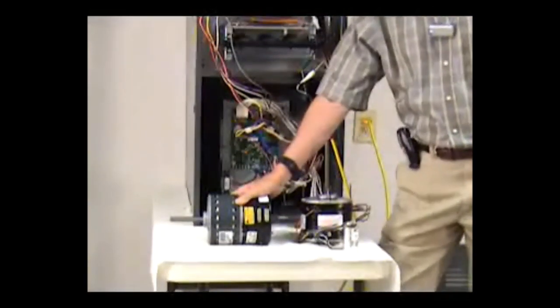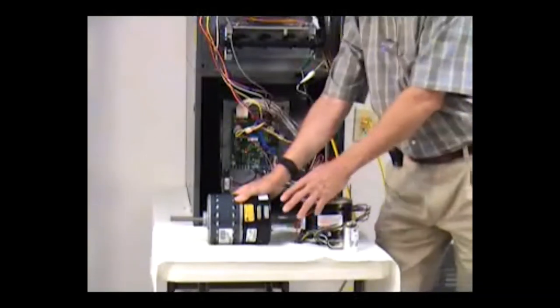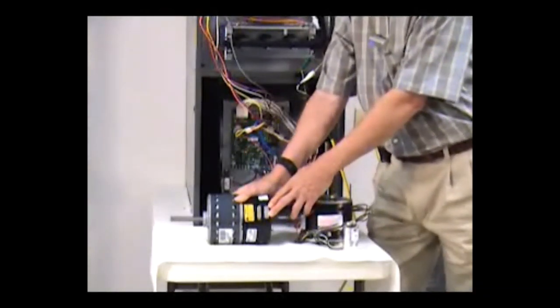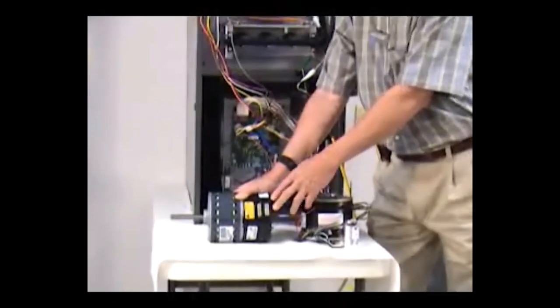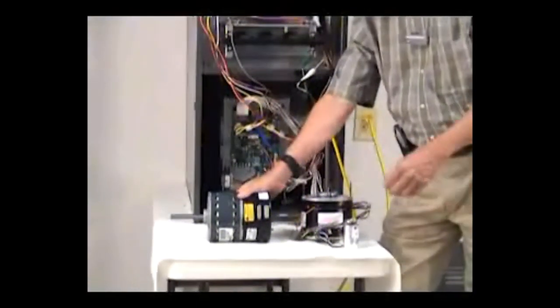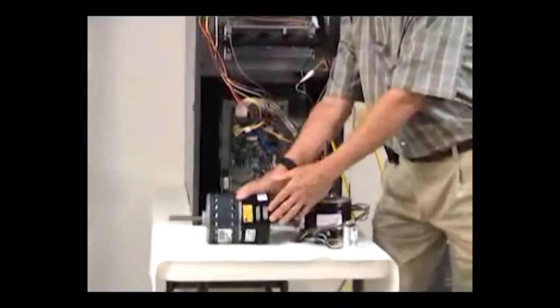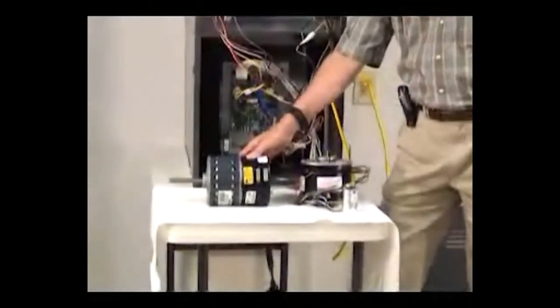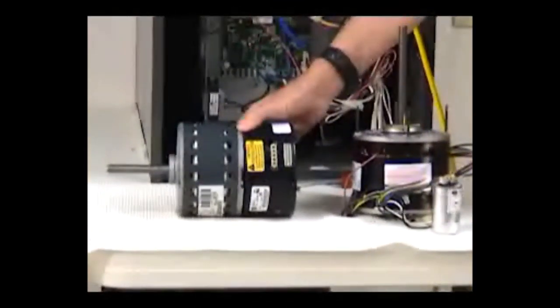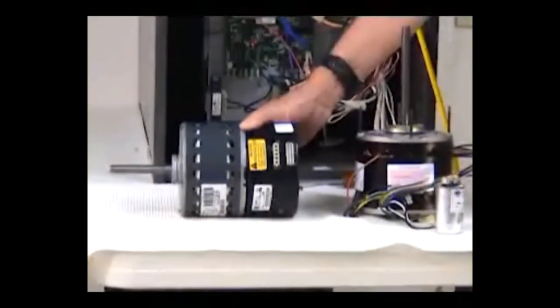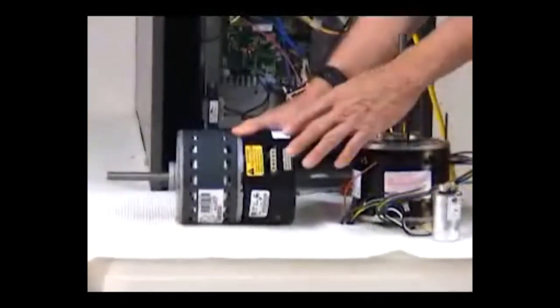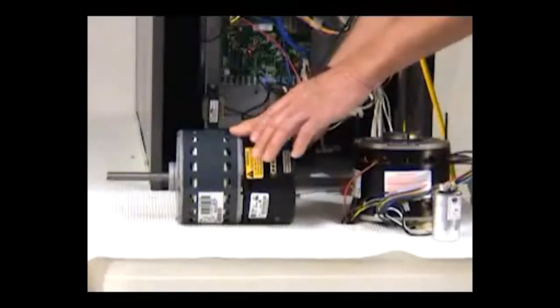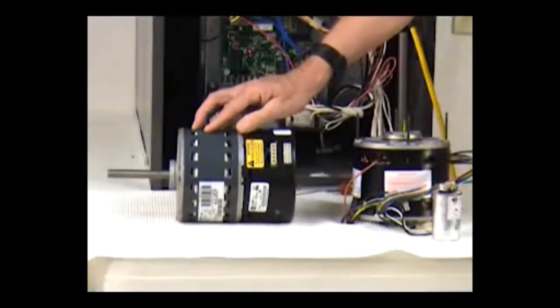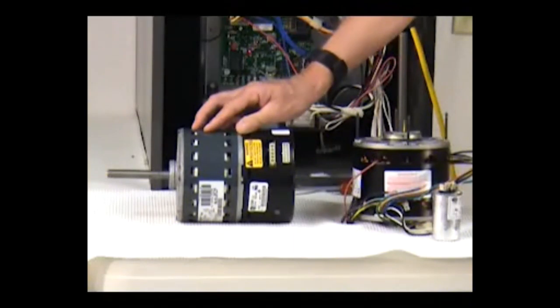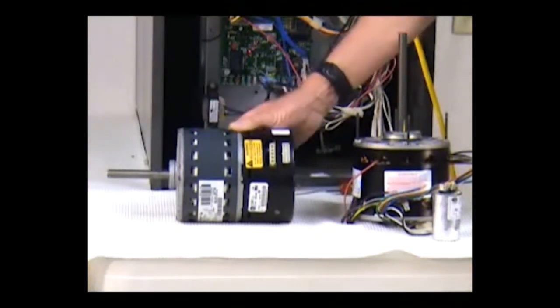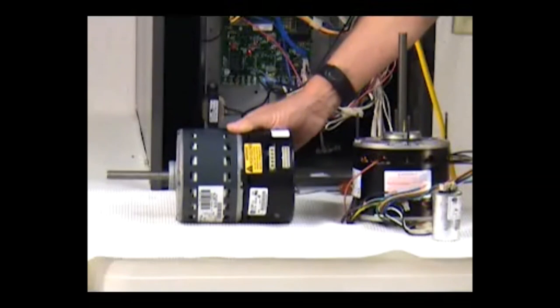The motor is variable speed. However, in this particular case, and for most of the applications that we are dealing with today, we're going to have a motor that will be sent from a thermostat to a board and then to the motor, which will select a specific motor speed that it will run in. Pulse modulation would also be applicable down the road and in the future, where this same motor can actually vary a speed up and down based on what is being told by that application.